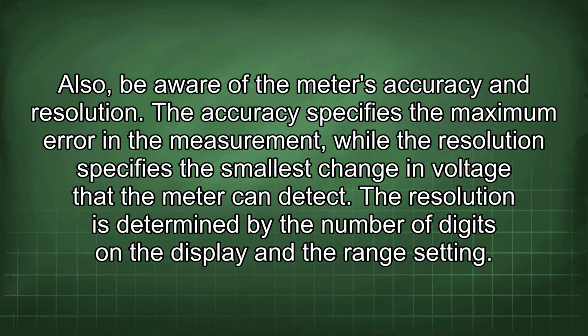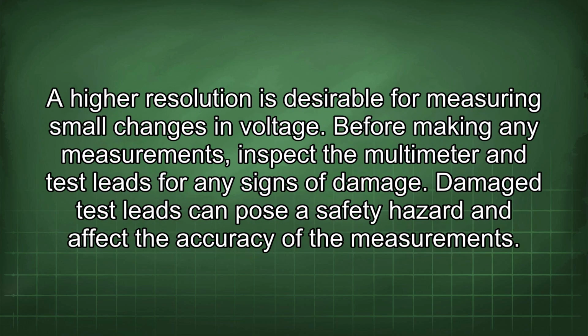Also, be aware of the meter's accuracy and resolution. The accuracy specifies the maximum error in the measurement, while the resolution specifies the smallest change in voltage that the meter can detect. The resolution is determined by the number of digits on the display and the range setting. A higher resolution is desirable for measuring small changes in voltage.